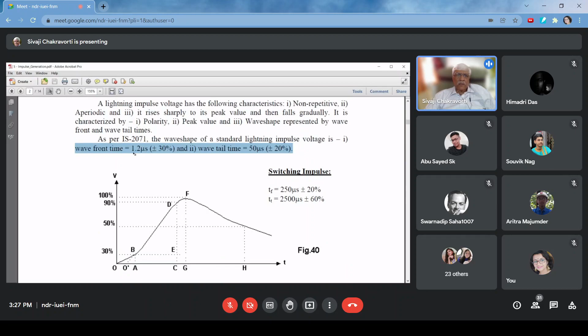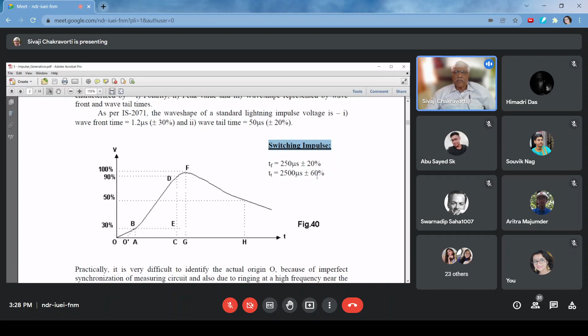There are impulse waves which are caused due to switching impulse. Switching impulses are much slower, not as fast as lightning impulse, because you can see lightning impulse, the front time is as low as 1.2 microsecond. So if you take 1 by t, which gives its equivalent frequency to be of the order of 1 megahertz. But switching impulse, the front time is of 250 microsecond with a tolerance of plus minus 20%. The tail time is 2500 microsecond, tolerance of plus minus 60%.